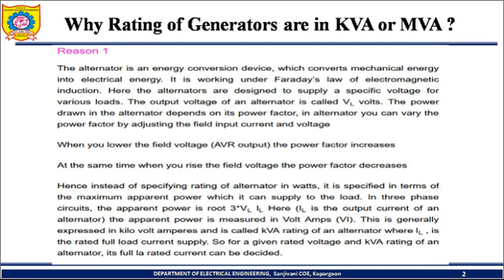Hence, instead of specifying the rating of an alternator in watts, it should be specified in terms of apparent power. Apparent power is nothing but voltage multiplied by current. Or in a three-phase circuit, we can say root 3 multiplied by line voltage multiplied by line current. So that's why this is generally expressed in terms of volt ampere or kilovolt ampere or MVA, megavolt ampere.